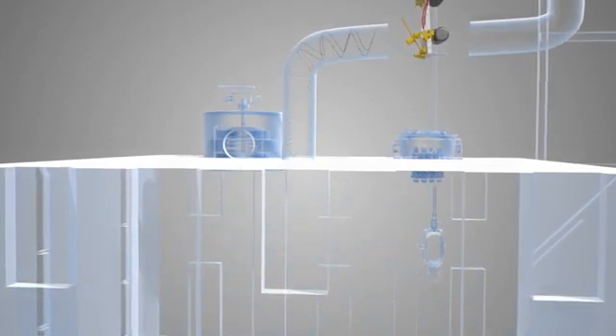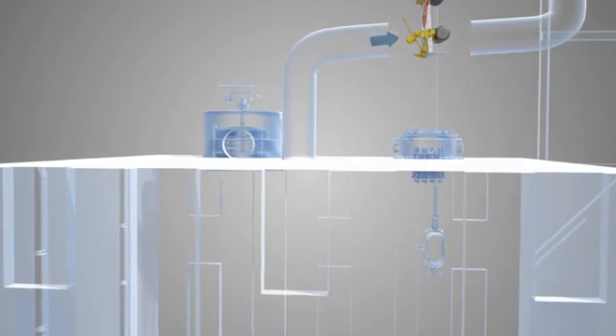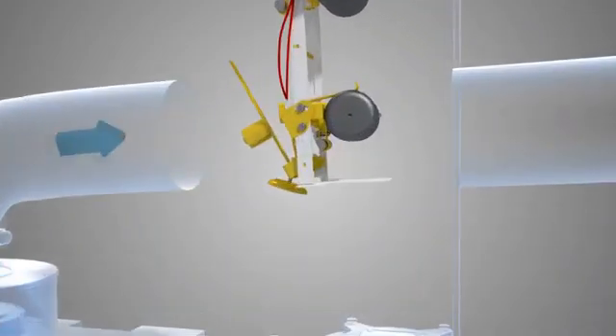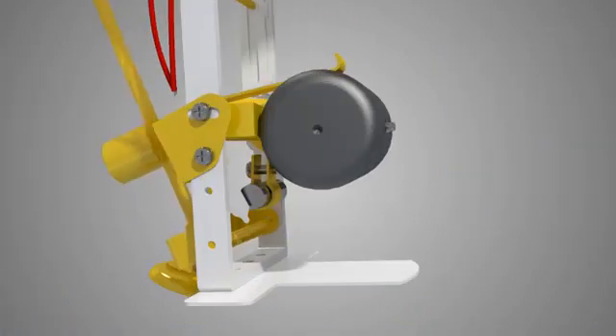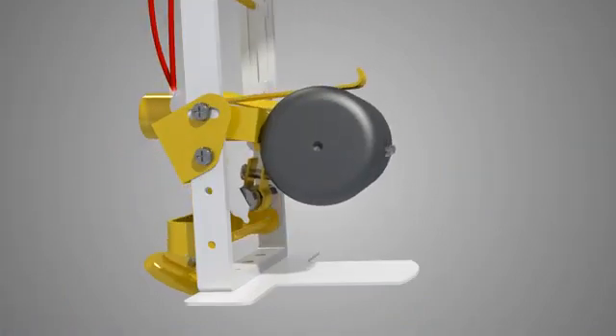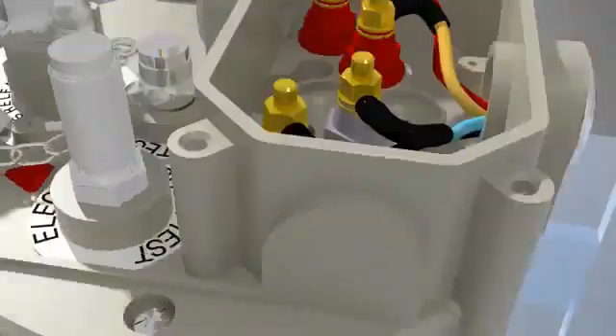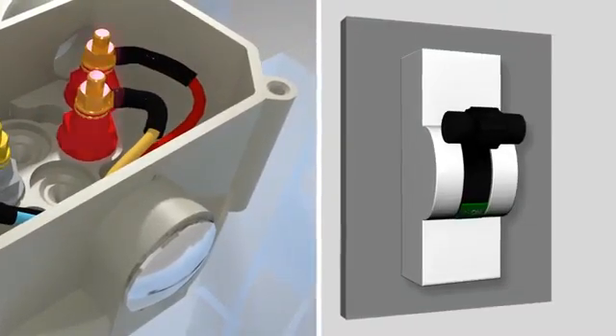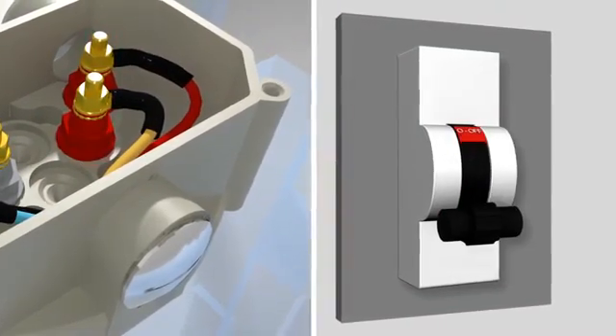Due to these pressure waves, the surrounding oil will rush through the connecting pipe towards the conservator. The Buchholz relay detects oil surge in the transformer and makes the trip system to operate.